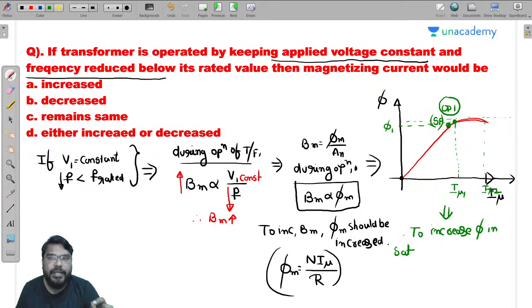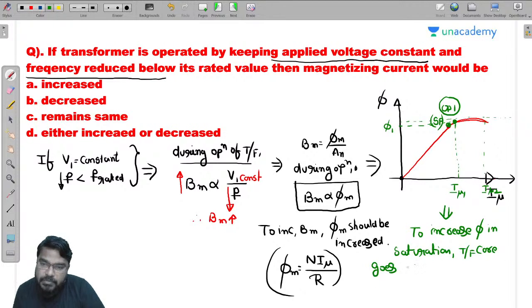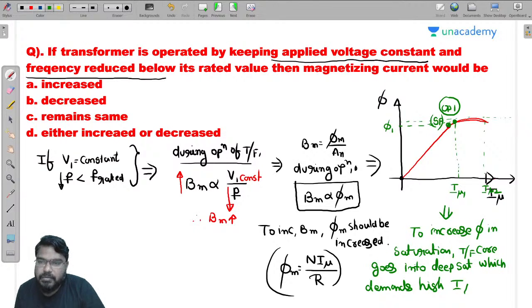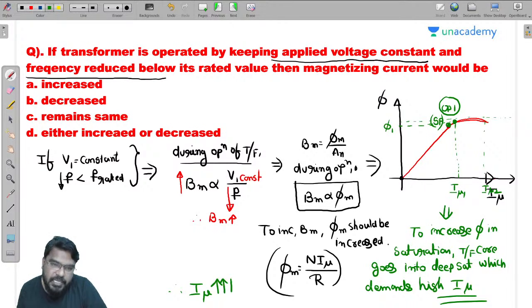this is the operating point 1. Initially it is operated at rated voltage condition. If the transformer is operated at less than the rated frequency, the transformer core goes into deep saturation. Deep means a very large amount of magnetizing current, which demands high magnetizing current. Got it? So what is the answer here? The magnetizing current of the transformer increases by a very large amount.